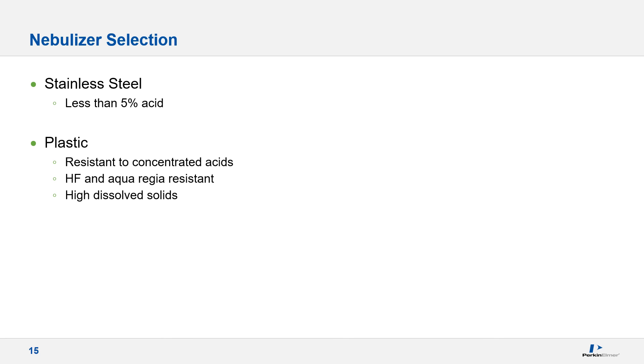Consideration should be given to the nebulizer selection process. In order to provide efficient nebulization for a variety of sample types, more than one choice is required. Stainless steel has been the most commonly used material, offering durability, low cost, and works well with organic solvents, but is susceptible to corrosion from samples with high acid content, creating analytical issues for elements such as nickel or chromium. For such cases, nebulizers constructed of corrosion-resistant materials such as inert plastic, platinum alloys, or tantalum should be used.